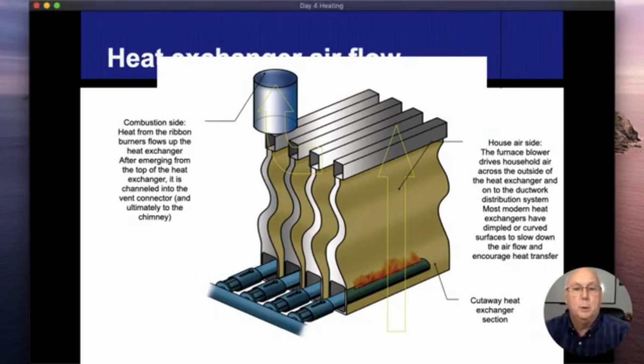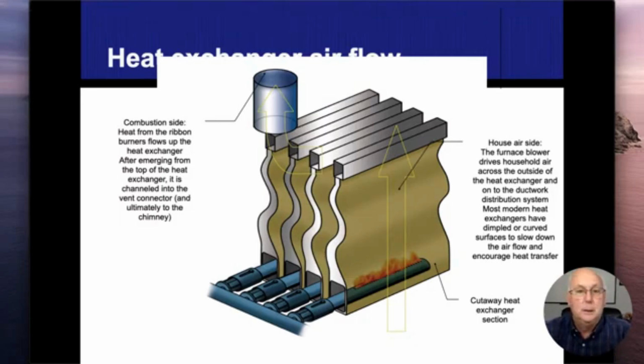So here's another shot of a heat exchanger, a little diagram. We can see where our burners are going in. It heats up the inside. This is typically how the old Lennox natural draft heat exchangers were. They would go kind of like a hula back and forth, and the heat would bounce off the different sides before it comes back up. And it's that opening where the burner comes in that you look right on the underside of, and that's where you find it. But again, we just don't see these anymore. I do want you to realize that the circulation air blows on the outside of the metal, where the bad gases are on the inside of the metal.